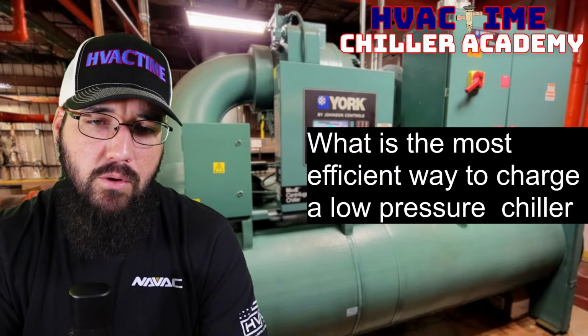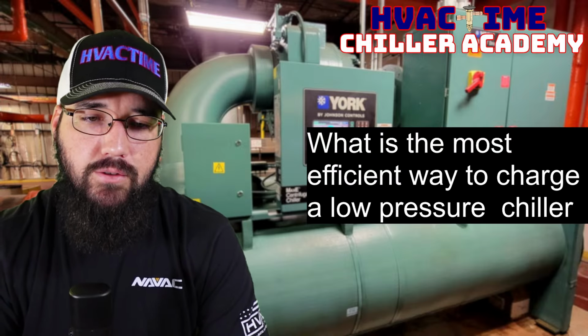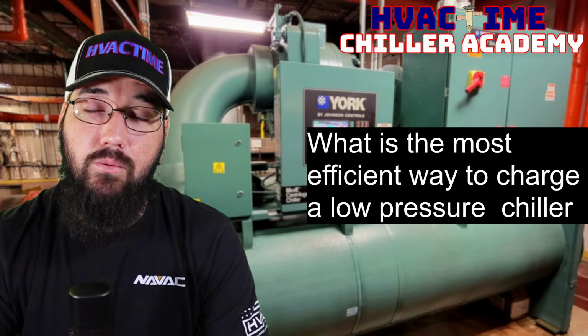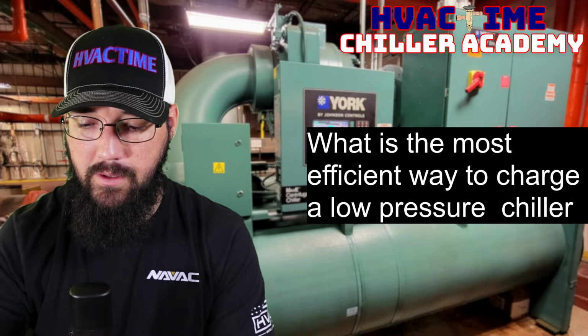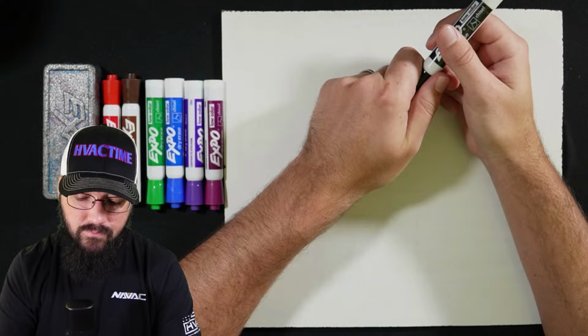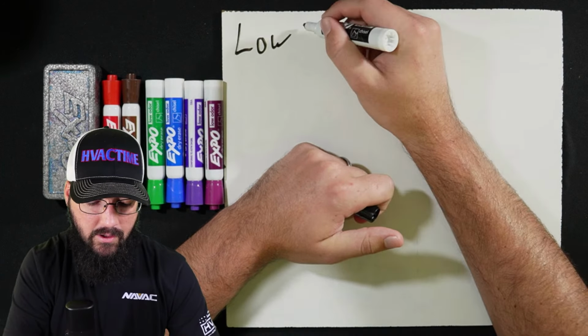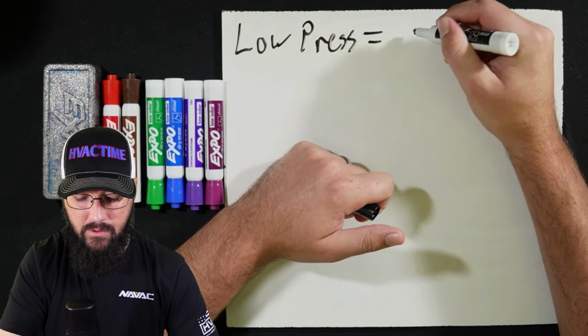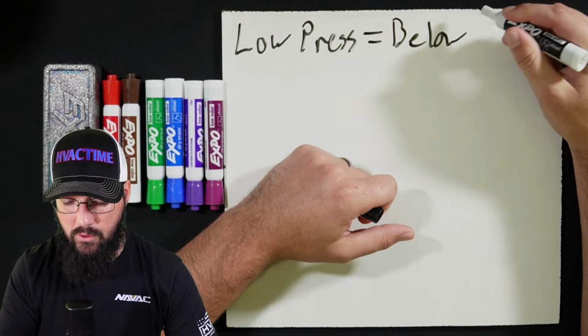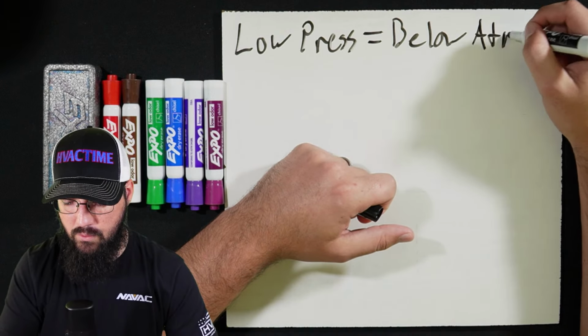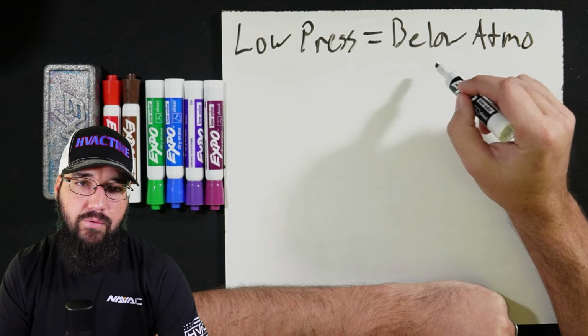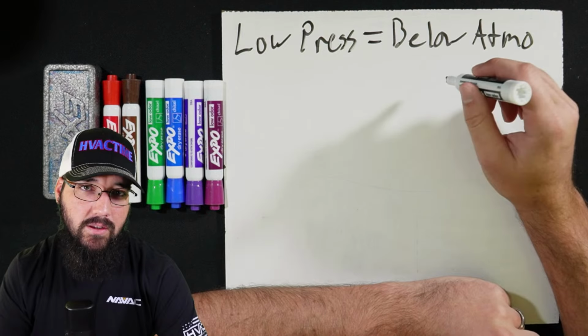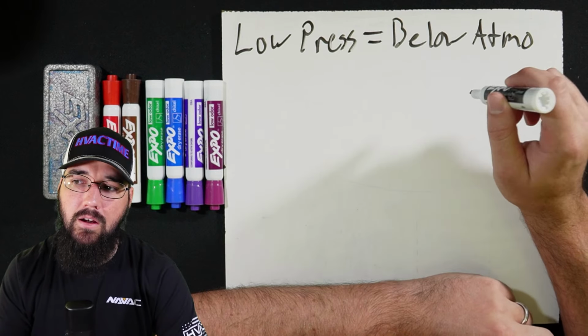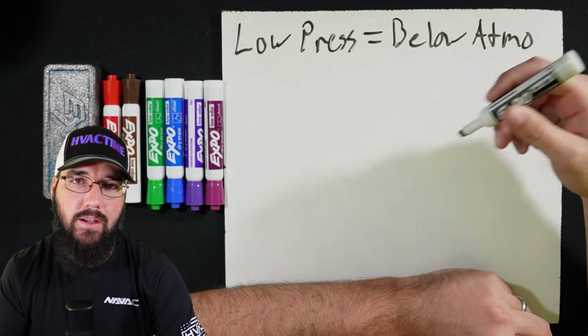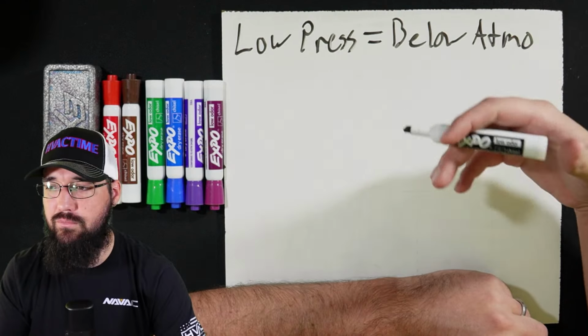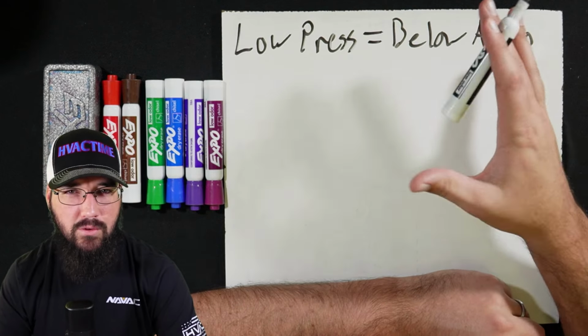With that, what is the most efficient way to charge a low pressure chiller? Let's start off with some very quick basics here, just so that we can keep everybody up to speed. When we say low pressure, we're talking about it operates below atmosphere. So that is a low pressure refrigerant. The refrigerant itself in operation is below atmosphere, especially in the evaporator. Sometimes on these, the condenser side can increase in pressure and get a little bit above atmosphere, so you may have 2, 3, 4, 5 psi in some cases. It also depends on the refrigerant.